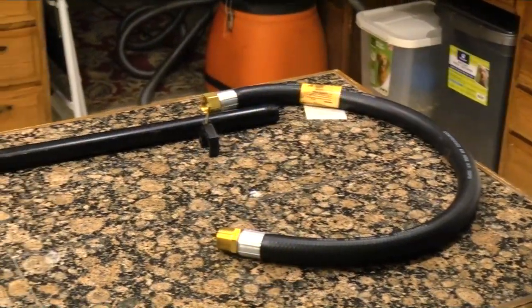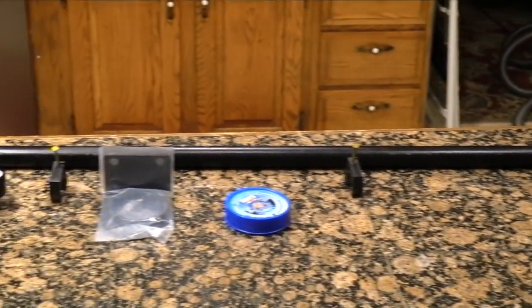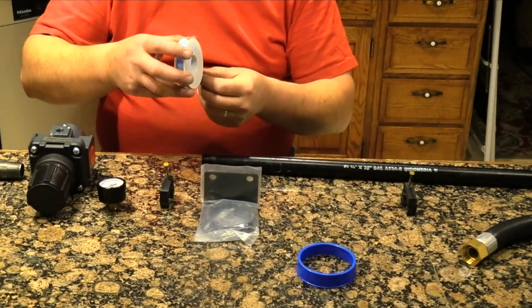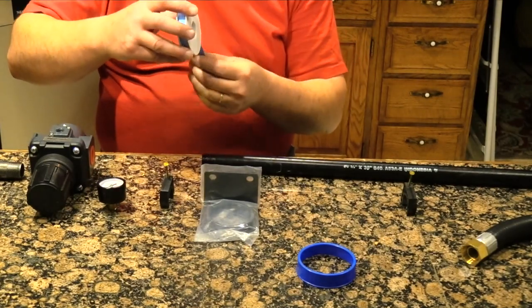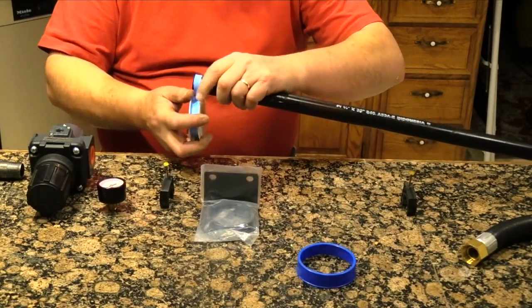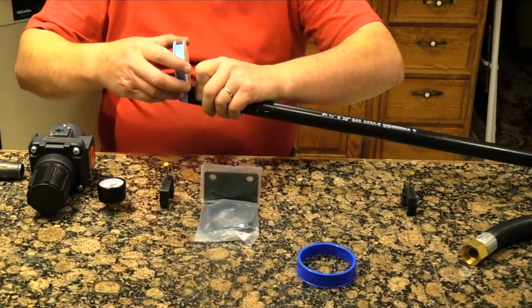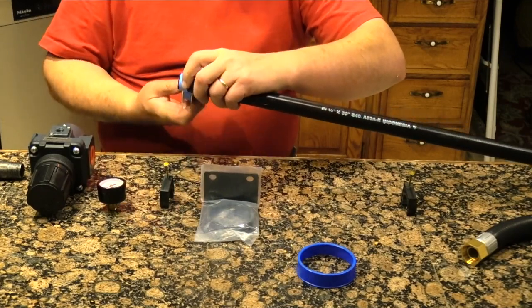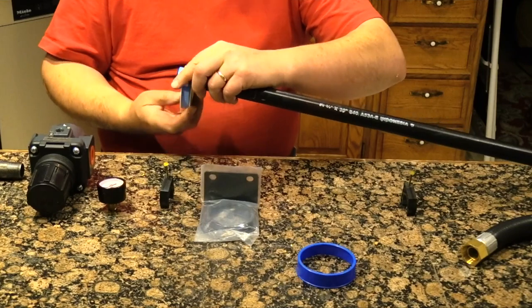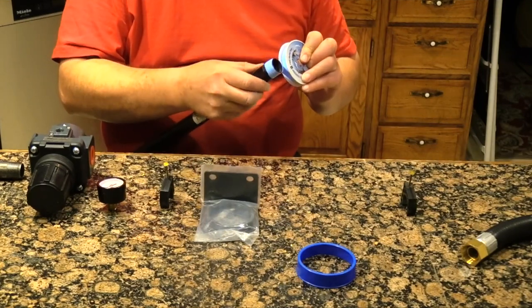I methodically laid out all the components of the wall mounted manifold. Then I began my assembly line process by wrapping all the male threads with teflon tape. I held the tape with my thumb and then unspooled the tape backwards around the pipe pulling tightly as I went. To prevent leakage three full wraps around the pipe are recommended.